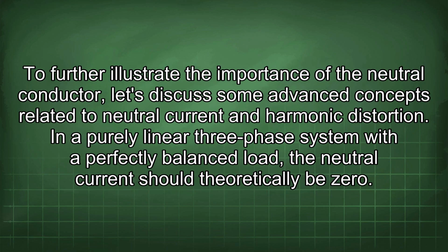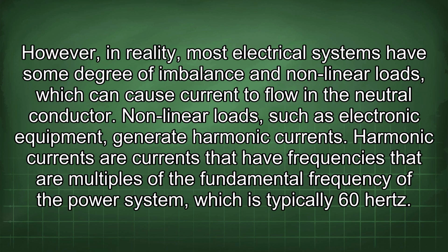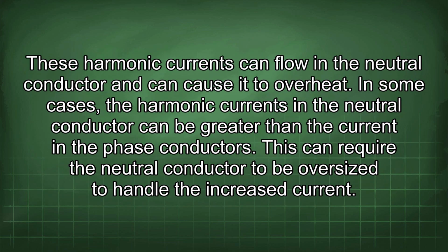To further illustrate the importance of the neutral conductor, let's discuss some advanced concepts related to neutral current and harmonic distortion. In a purely linear three-phase system with a perfectly balanced load, the neutral current should theoretically be zero. However, in reality, most electrical systems have some degree of imbalance and non-linear loads, which can cause current to flow in the neutral conductor. Nonlinear loads, such as electronic equipment, generate harmonic currents. Harmonic currents are currents that have frequencies that are multiples of the fundamental frequency of the power system, which is typically 60 Hz. These harmonic currents can flow in the neutral conductor and can cause it to overheat.